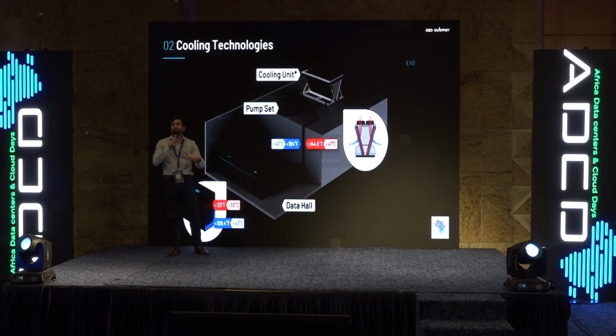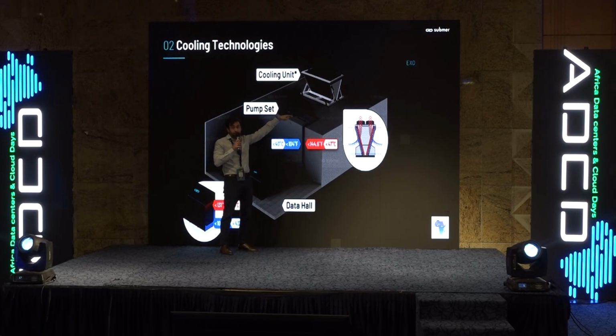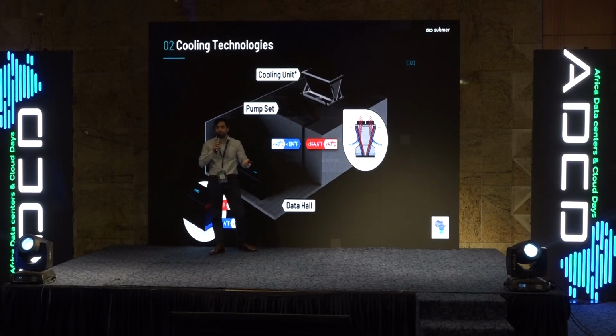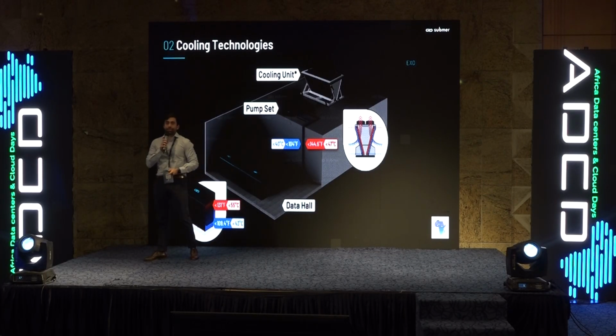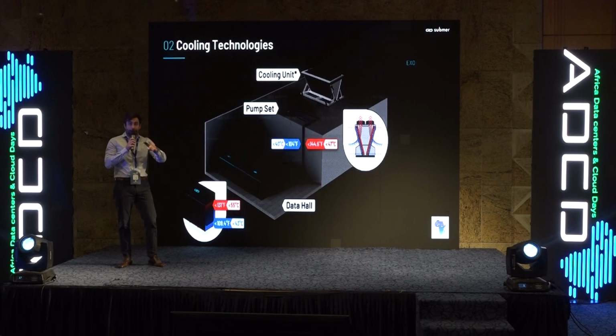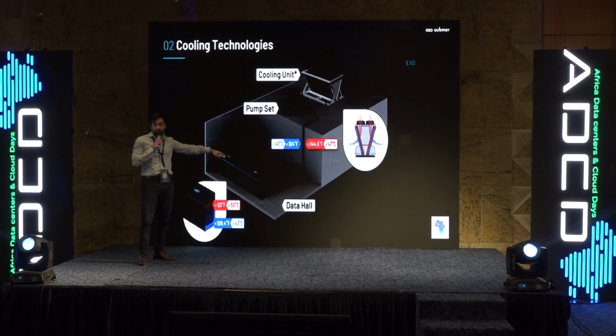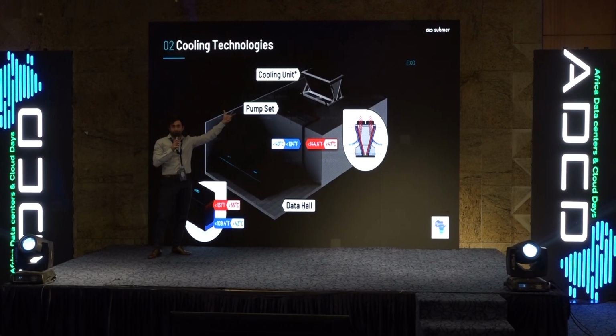So it's what they call heat reuse or heat recovery. In the end, you are always going to dissipate the heat to the ambient. The only way to avoid that is basically changing that dry cooler for a heat recovery application such as district heat. That's a way you can reuse this type of technology, and by the way, this happens not only with immersion but also with air cooling and DLC. You always need to dissipate the heat to the ambient or to a heat recovery application.